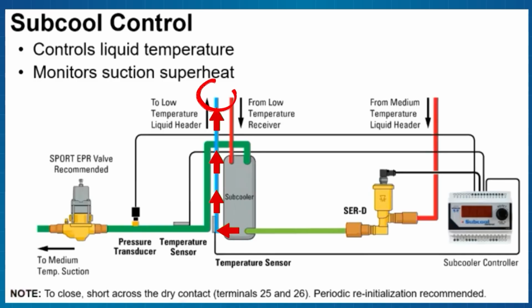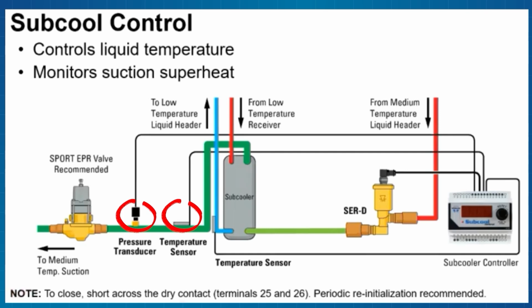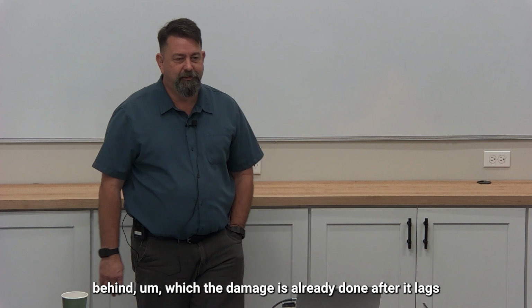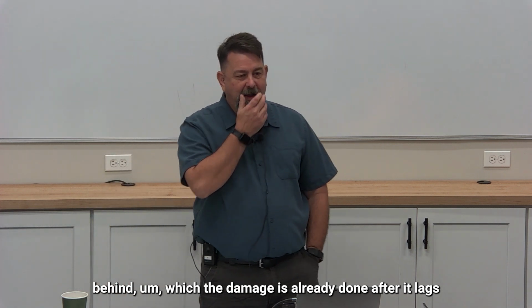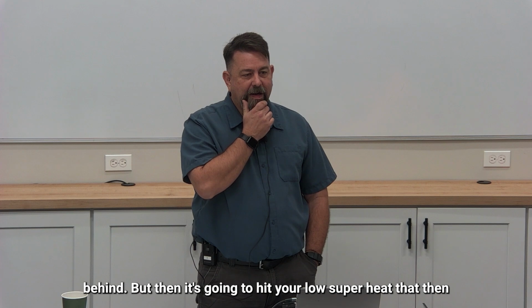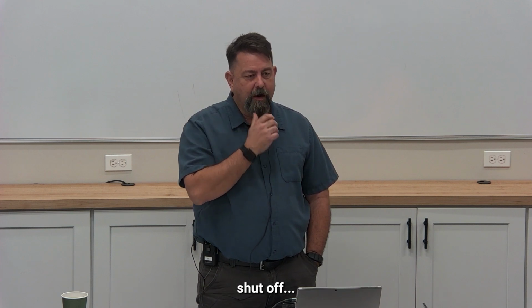Now my line sits there at 49 degrees all night. First thing in the morning, it starts warming up, goes to 51. Solenoid opens. What percentage? 100%. Am I gonna flood? Oh yeah. What's that gonna look like down here? The pressure's gonna be higher. Is this controller gonna see that it's flooding? No, it will, but it's gonna lag behind, and the damage is already done after that. It lags behind, but then it's gonna hit your low superheat, that shuts off, and it's gonna go all the way to zero.